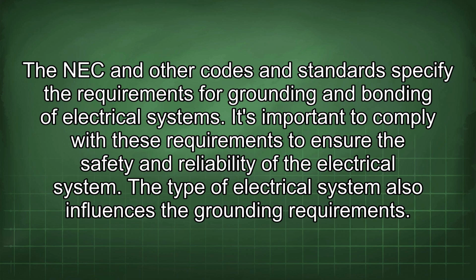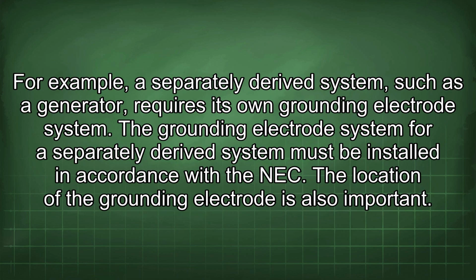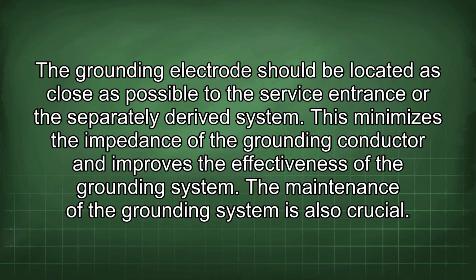The type of electrical system also influences the grounding requirements. For example, a separately derived system, such as a generator, requires its own grounding electrode system. The grounding electrode system for a separately derived system must be installed in accordance with the NEC. The location of the grounding electrode is also important. The grounding electrode should be located as close as possible to the service entrance or the separately derived system. This minimizes the impedance of the grounding conductor and improves the effectiveness of the grounding system.